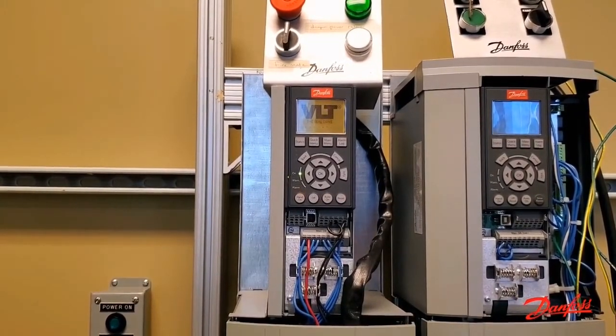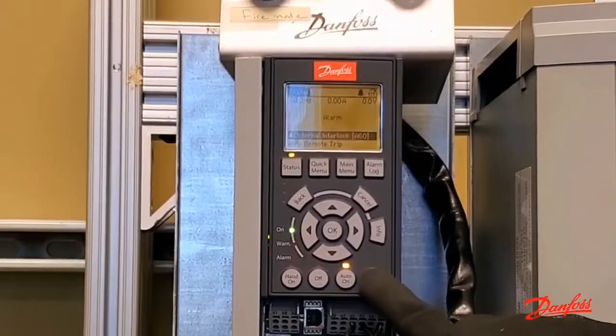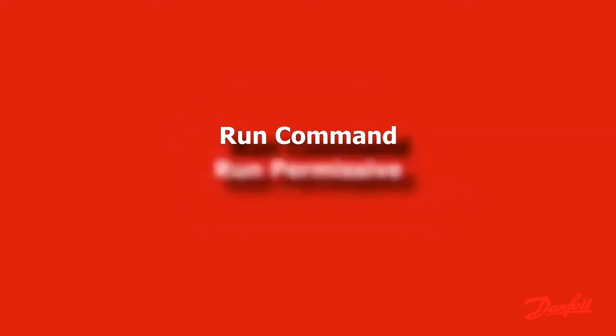If you're still unable to run, there's a good chance you're missing one of the three main signals the panel requires: run command, run permissive, and external interlock.